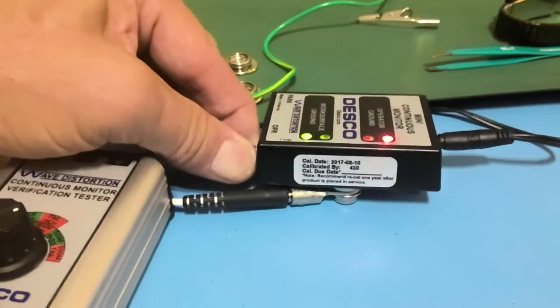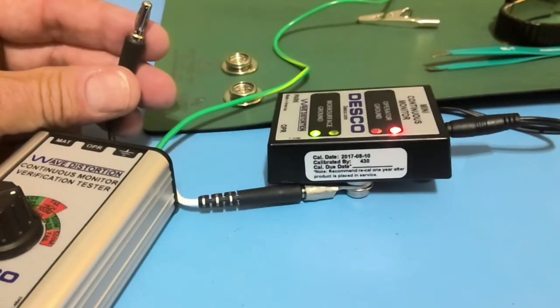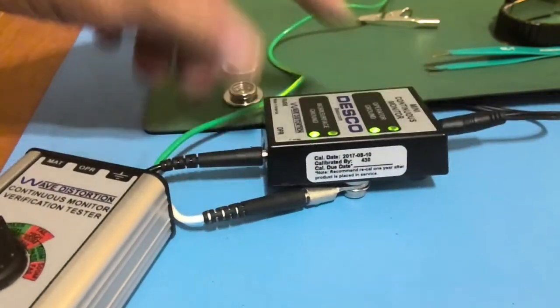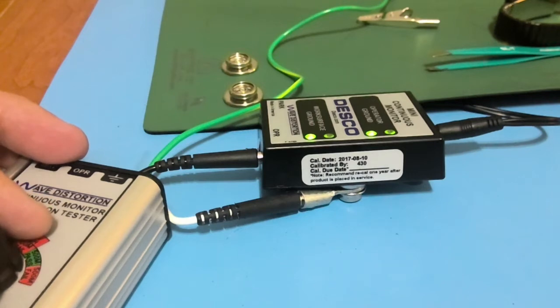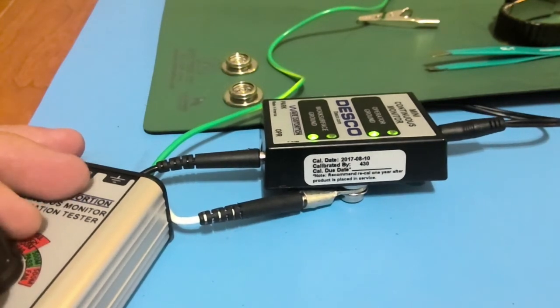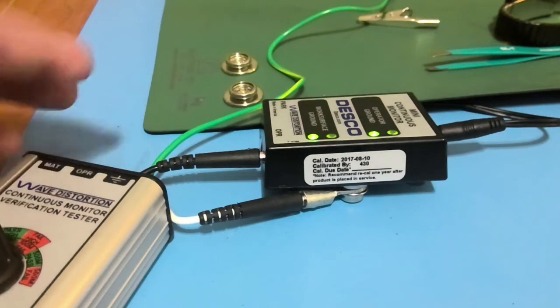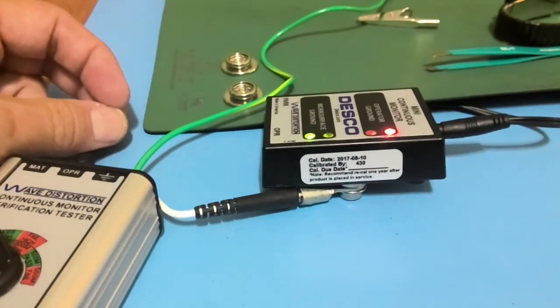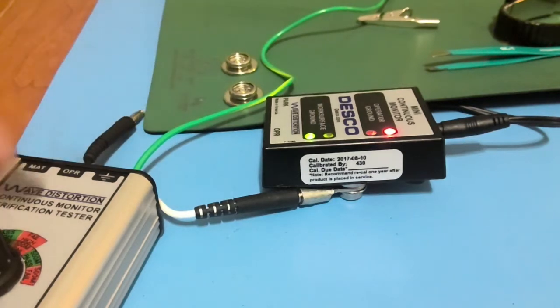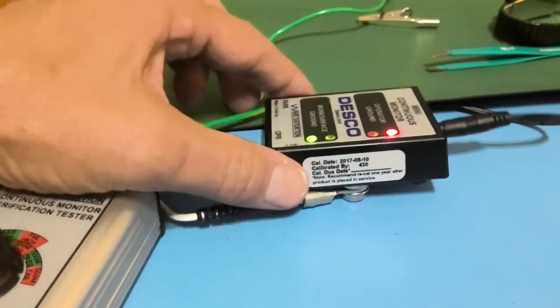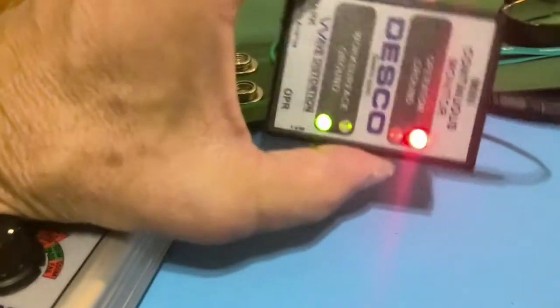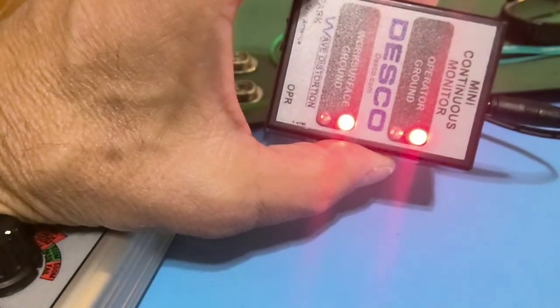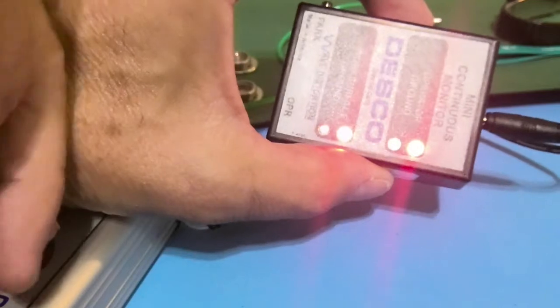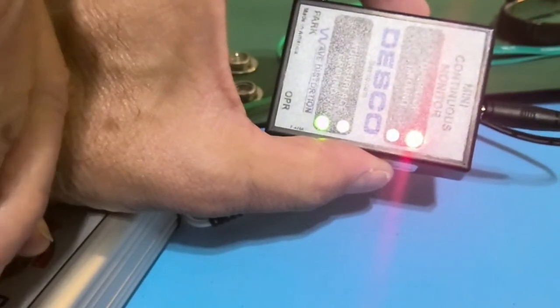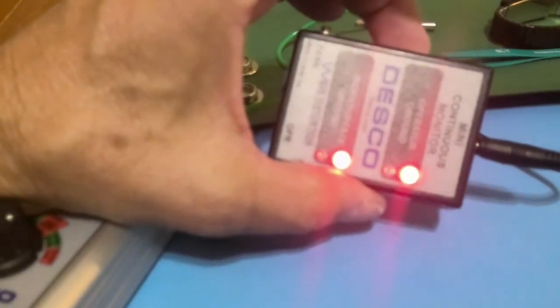That's pretty much it. The operator cord, if you leave it plugged in, you don't get all the alarms, but you can unplug it if that bothers you. The instructions don't really say either way, but to keep it from beeping, if you unplug this and give it a moment, it will stop beeping, and then you can do your mat test. But as you saw, it doesn't really matter whether the operator cord is in or not. It's still going to work: that's hot, that's fail, that's pass, that's fail. Okay, that's all there is to it. Piece of cake.